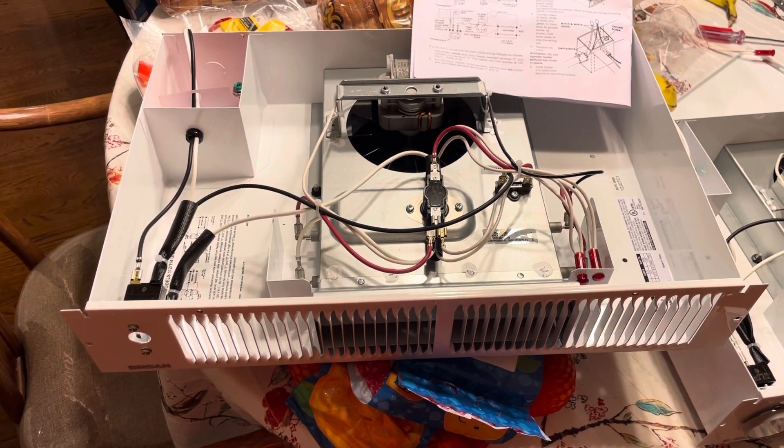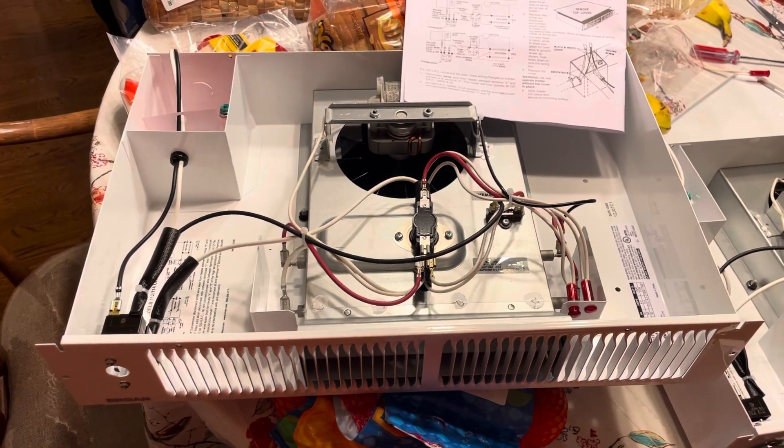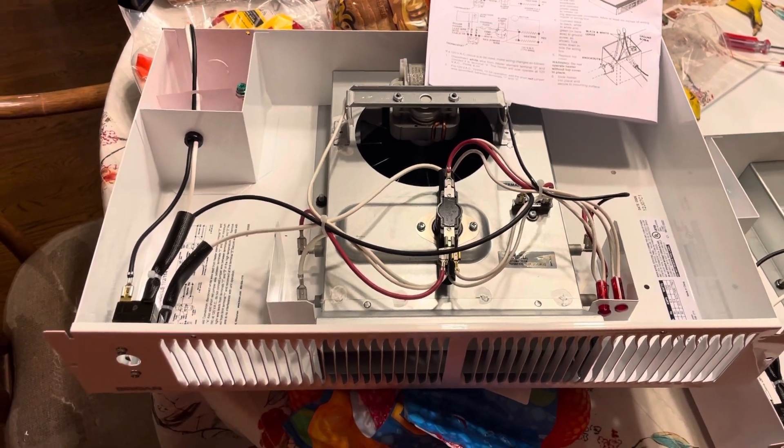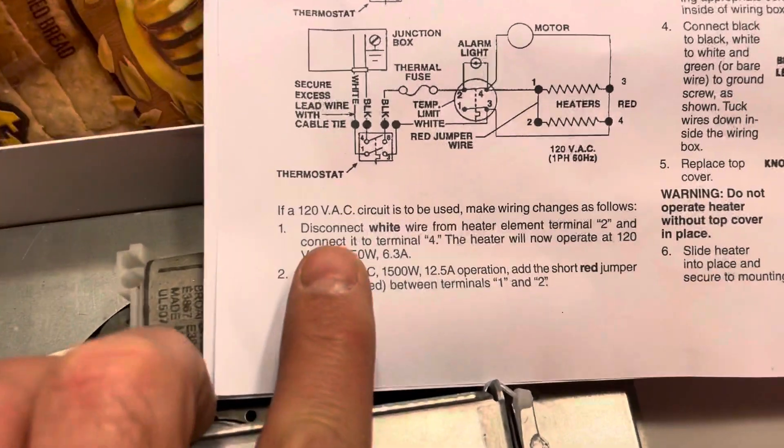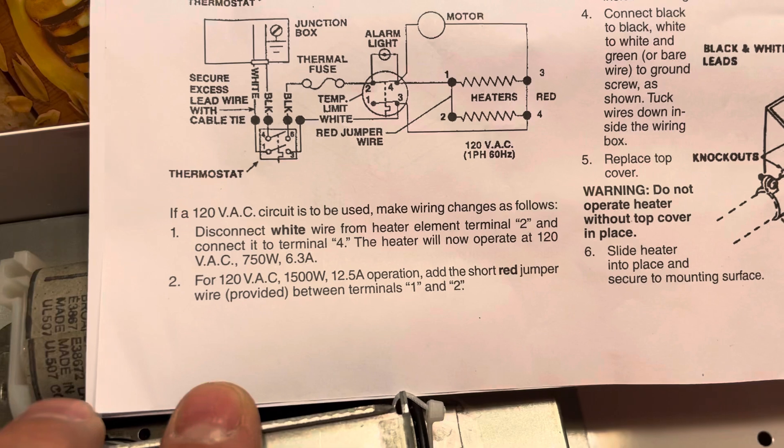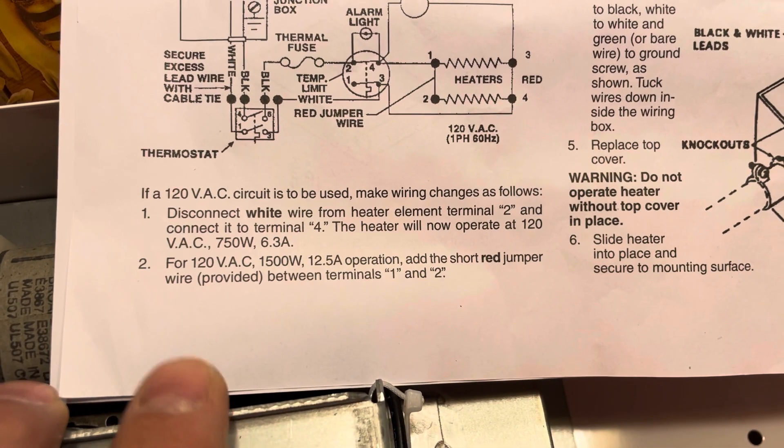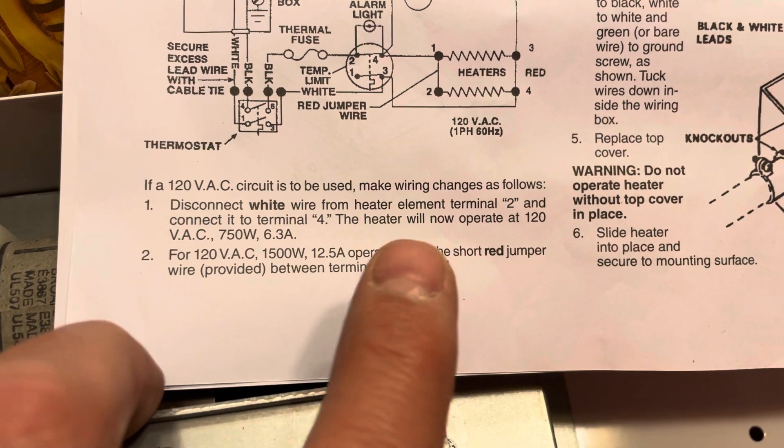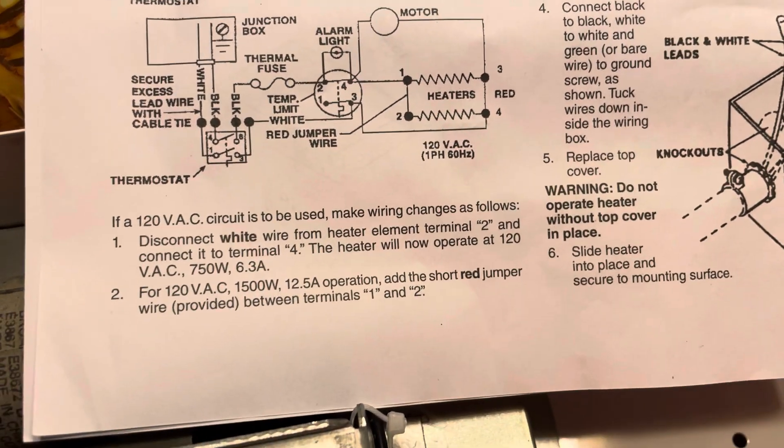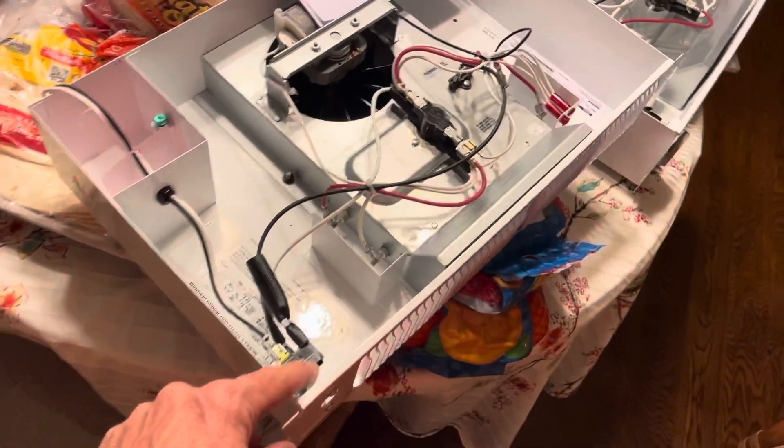And then also be able to alternate between 750 watts and 1500 watts of operation. So here we go. The first thing you do is if 120 volts AC circuit is to be used, make wiring changes as follows: disconnect the white wire from heater element terminal 2 and connect it to terminal 4.